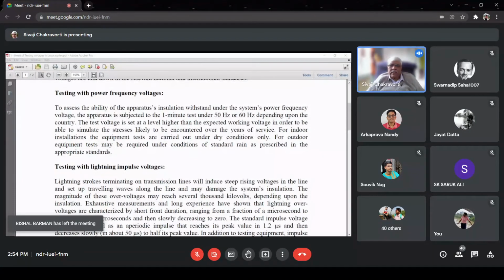And then you can ask me the next question. In a power system, the transformers or the generators will be running 24 by 7. So how long will we test? That's an important question. The answer is very simple. This has been studied a lot and it has now been standardized that we test it for 1 minute. So it is called the 1 minute power frequency test.